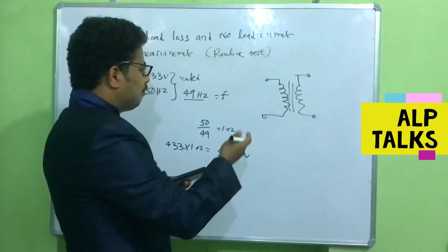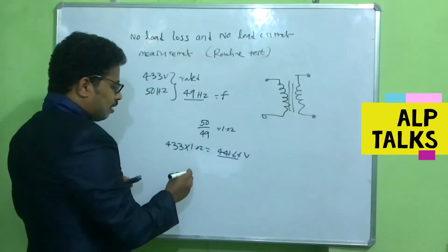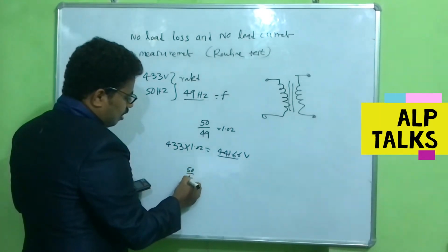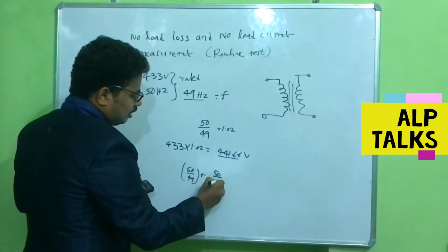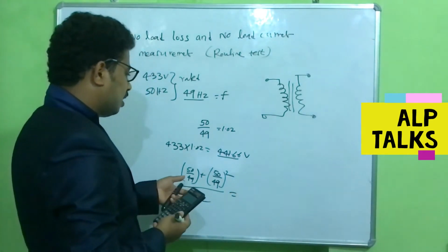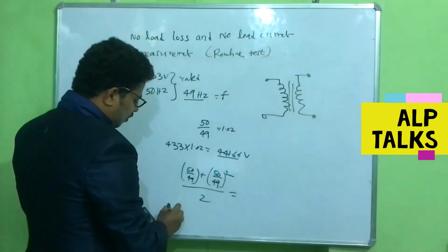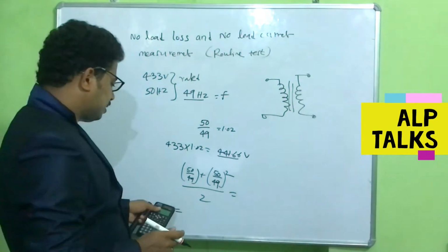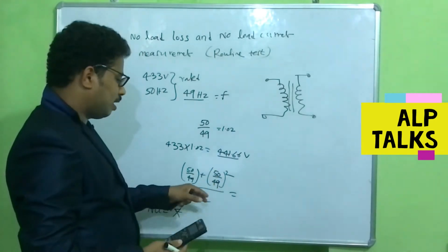Then the meters will give us readings. Let's see. Here we have another parameter for calculating no load losses. We have one ratio here, and this is just an empirical formula. Most of the companies or factories use these parameters for correcting the no load losses. So whatever no load loss is measured, we should multiply that no load loss with a factor we are going to derive now.